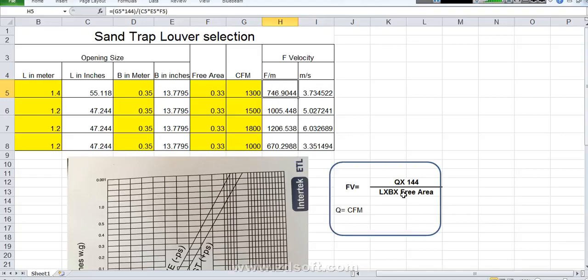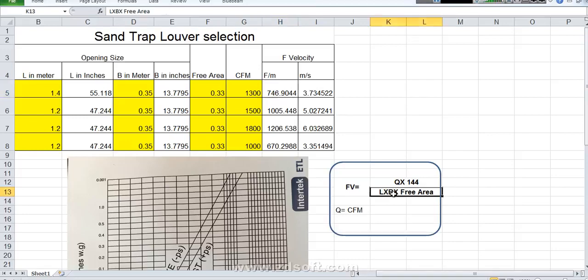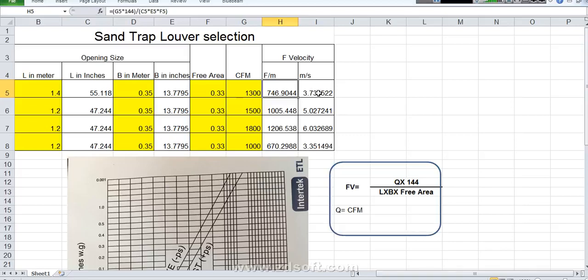This equation is very simple. Q is CFM times 144 divided by length in inches, length and breadth and free area. Free area as I told you. If you put this one you will get feet per minute. And if you want to convert this feet per minute into meter per second you need to put times 0.005. Then you will find it what is the meter per second face velocity.